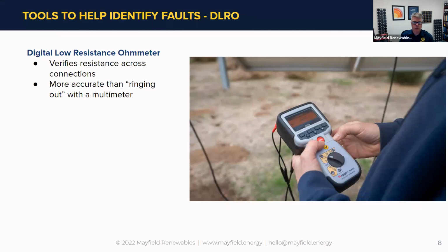Mike, talk us through what this is and where it's been useful. This is the tester that gets back to that picture where we showed the lay-in lug that was getting corroded. We were in the field using this tester on a ground mount array with old 285 watt modules or so. We had lugs from one module on one side and another module on the other side, less than 3 feet apart, connected with bare copper, and we were not able to get a continuity check on those.